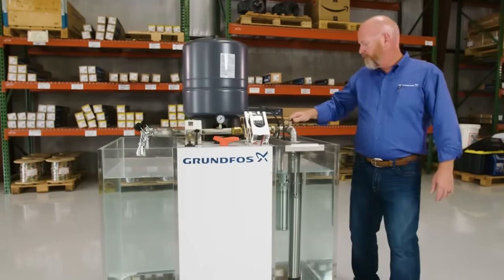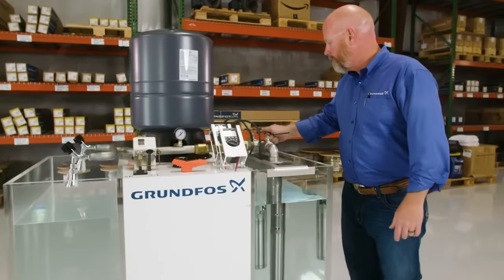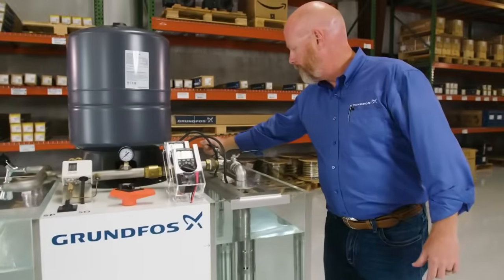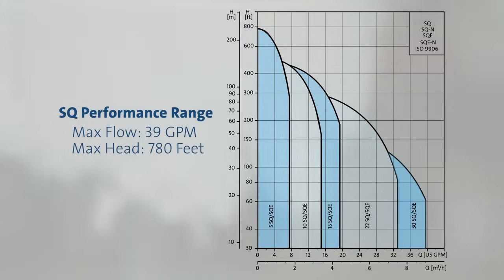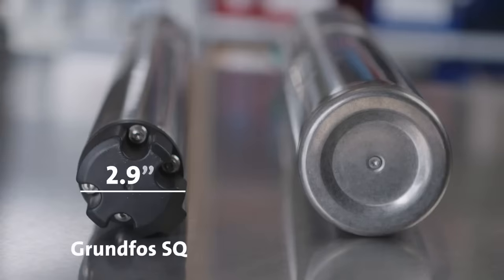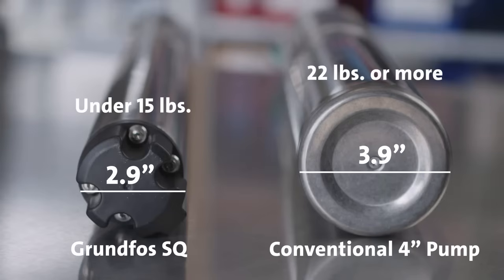The SQ pump was launched by Grundfos in 1999 and is unique in the industry for its diameter and built-in protection features. This reliable submersible pump is available in five flow rates and delivers up to 39 gallons per minute and 780 feet of head. The SQ combines a permanent magnet motor controlled by a micro frequency converter and a 2.9-inch diameter pump end into a submersible pump that weighs under 15 pounds.